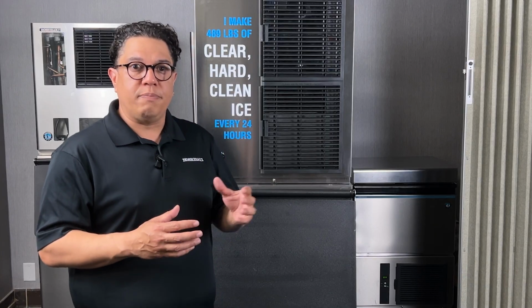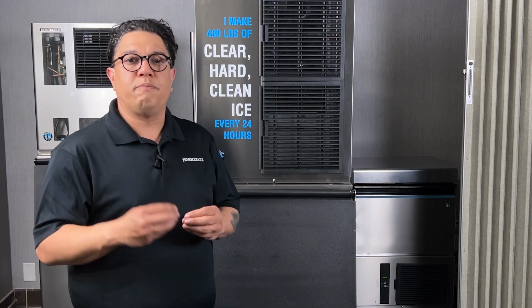The transformer that's inside of the control box, if we have 115 volts going into it, it's going to push out 10.5. But if the voltage is a little bit lower, like 90 volts, then the transformer is not capable of pushing out 10.5. It's going to push out something a little bit lower, like about 7.3 or 8.5. That's going to be too low, so the board is automatically going to go off on that 6 beep alarm, which is a low voltage alarm.